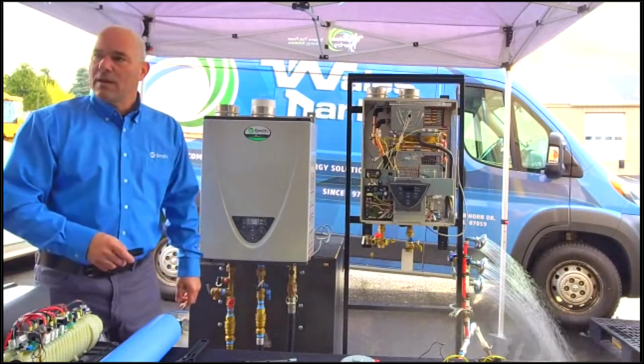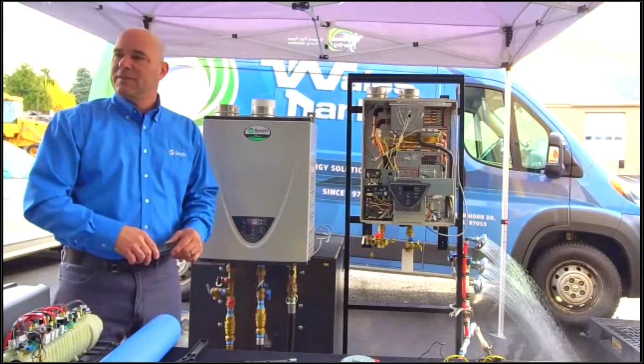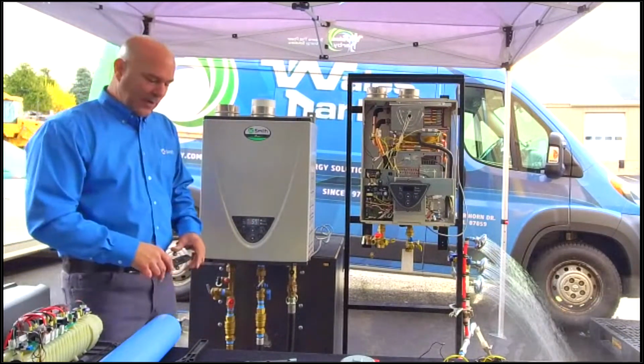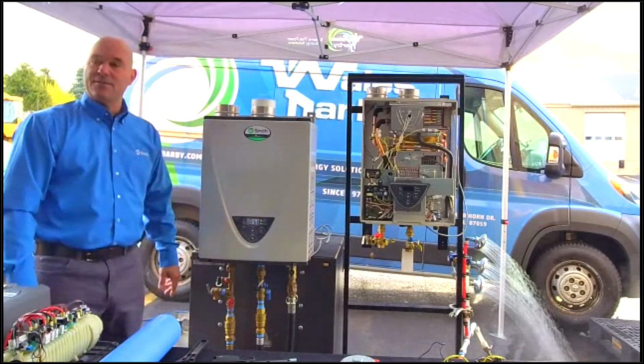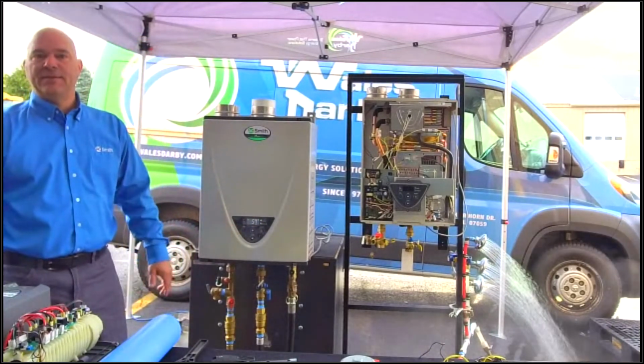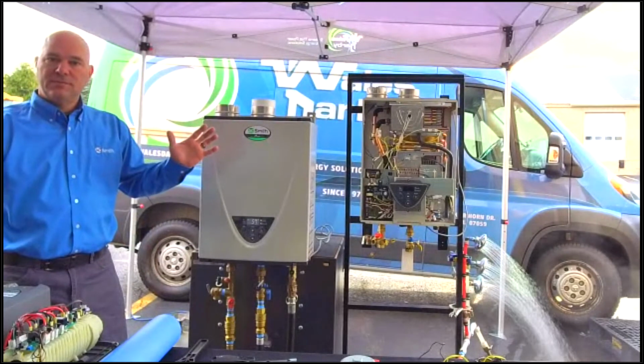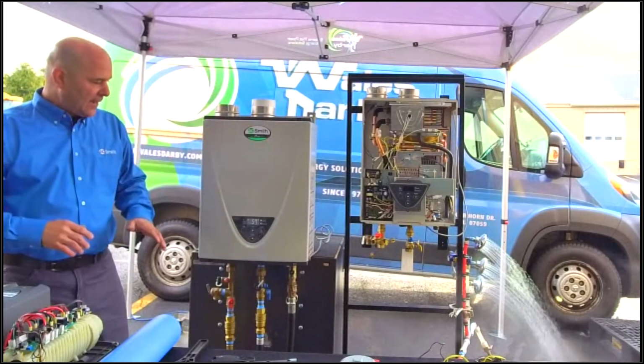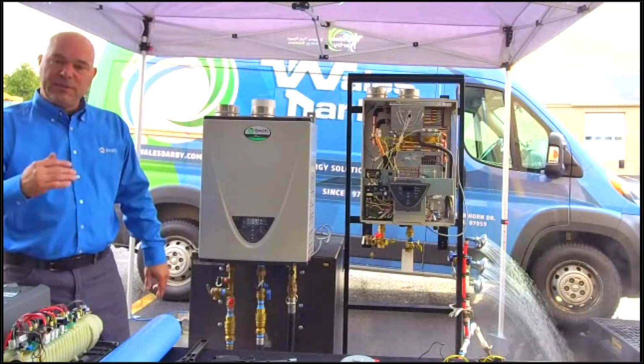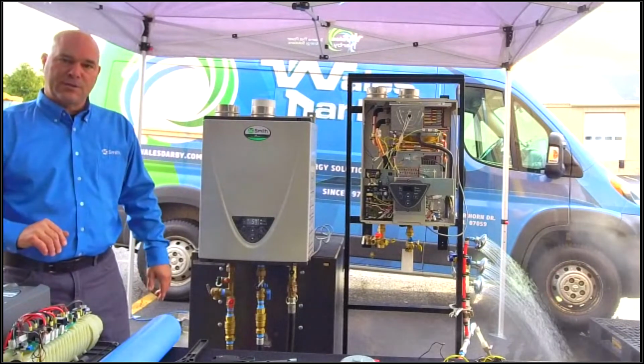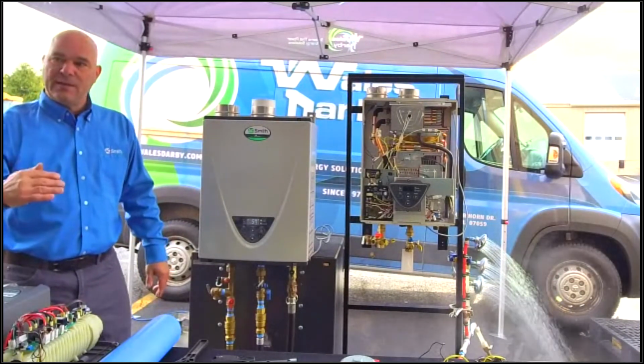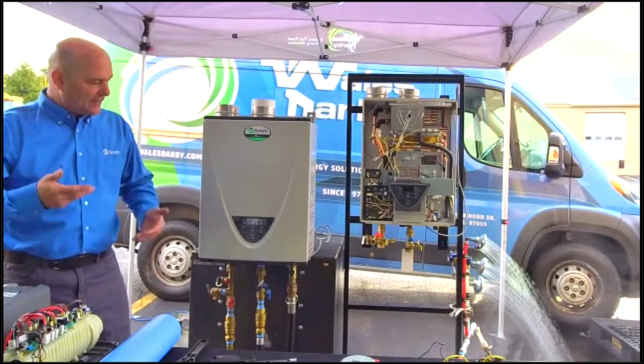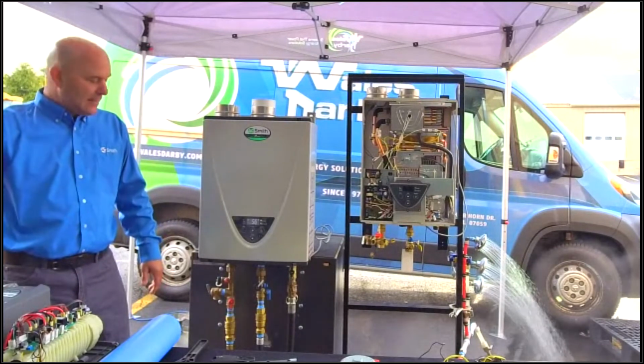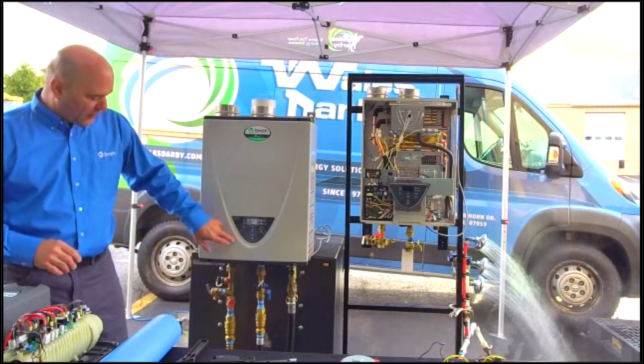Okay, so at 55 degrees with this 540, we could deliver 6.9 gallons of hot water a minute forever. So it's always going to be driven by the inlet water temperature. If I pull that inlet water temperature down where I have to get a full 70-degree rise, that's when I'm going to get down to the 5.4.